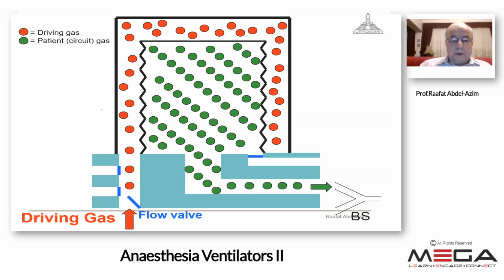We have 4 valves to operate the ventilator. These are the flow valve that should be opened during inspiration throughout the inspiratory time to allow the driving gas to come into the chamber to compress the bellows. The other three valves are the safety or the overpressure valve that opens if the airway pressure is high for any reason at any time of the respiratory cycle.